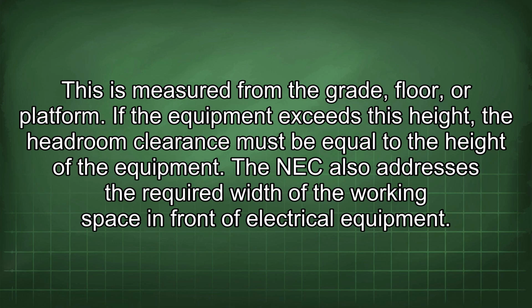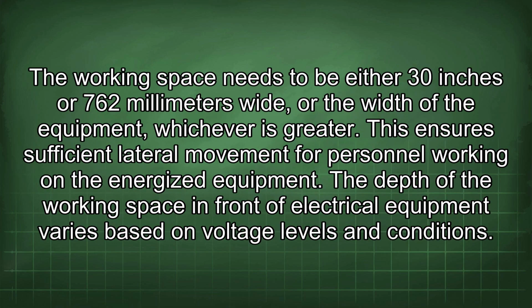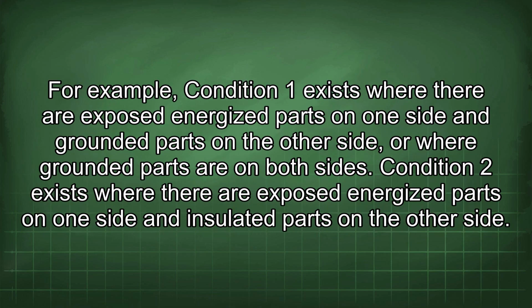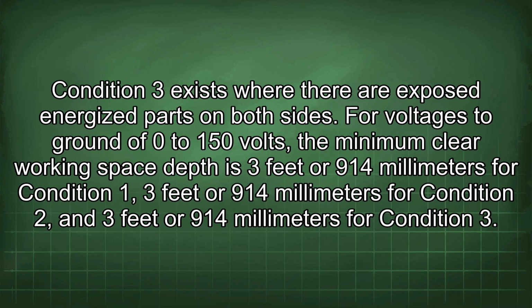The NEC also addresses the required width of the working space in front of electrical equipment. The working space needs to be either 30 inches or 762 millimeters wide, or the width of the equipment, whichever is greater. This ensures sufficient lateral movement for personnel working on the energized equipment. The depth of the working space in front of electrical equipment varies based on voltage levels and conditions. For example, condition 1 exists where there are exposed energized parts on one side and grounded parts on the other side, or where grounded parts are on both sides. Condition 2 exists where there are exposed energized parts on one side and insulated parts on the other side. Condition 3 exists where there are exposed energized parts on both sides.